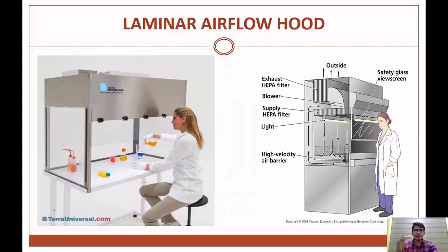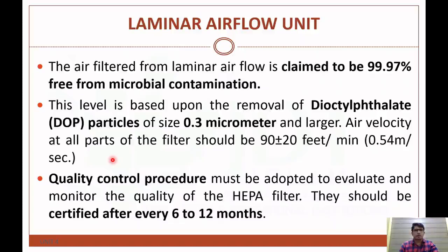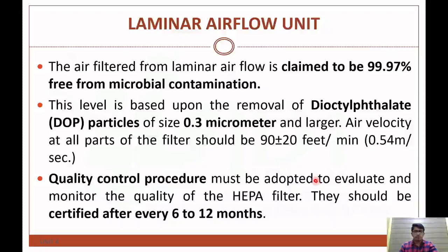Contaminating micro-organisms will be removed by the laminar air flow unit, and it is claimed to be 99.97% free from microbial contamination. This level is based upon the removal of di-octyl phthalate particles with a particle size of 0.3 micrometer and larger. The air velocity at all parts of the filter should be 90 plus or minus 20 feet per minute. The quality control procedure must be adopted to evaluate and monitor the quality of the HEPA filter, and it should be certified after 6 to 12 months of installation.